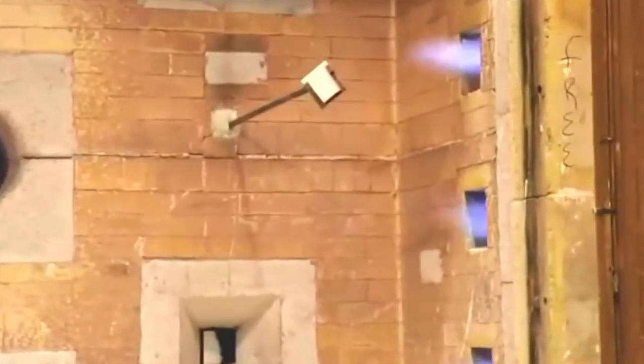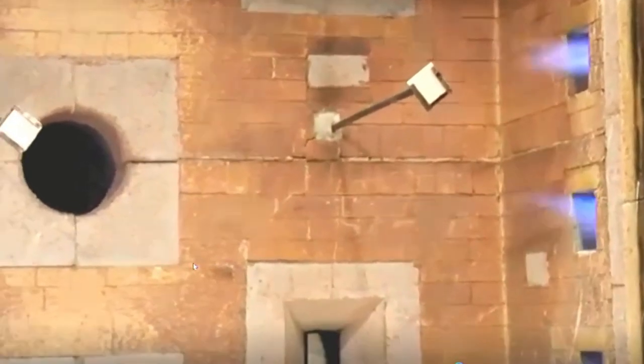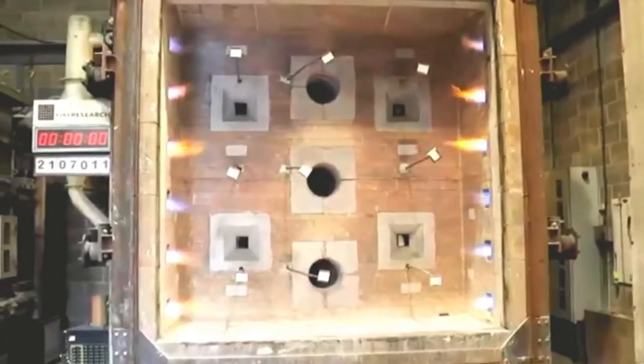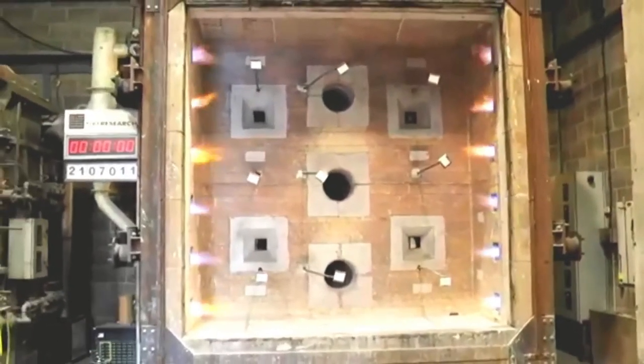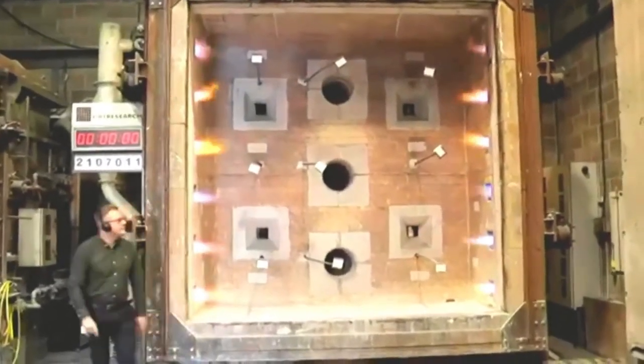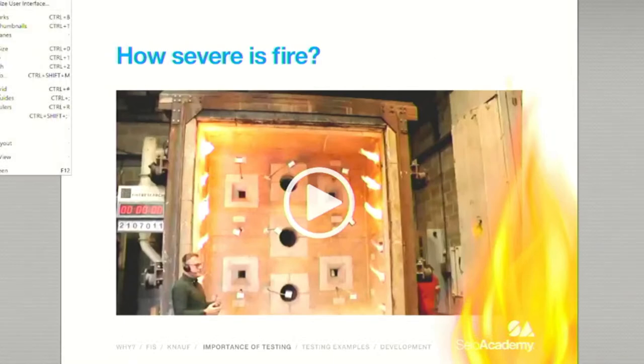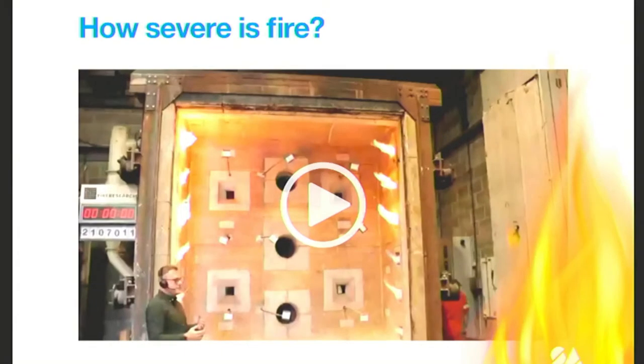So at 6 minutes, we'll be up somewhere about 660 degrees, just under the half an hour mark, over 850 degrees. When we get to an hour, just under 1,000 degrees hot. Then when we get to 2 hours, carry on to about 4 hours 20, it gets to 1154. Don't ask me how I know that. Give you an idea of what happens to the materials then. So timber typically combusts around 200 to 260 degrees, aluminium melts at 660 degrees, steel.